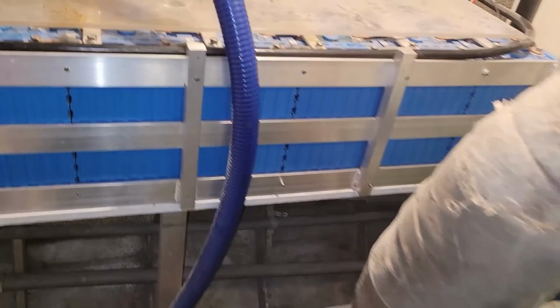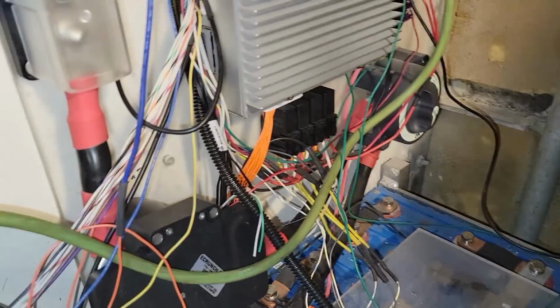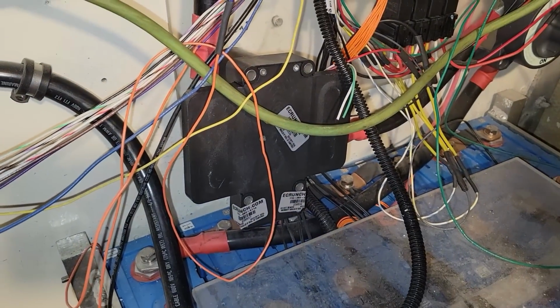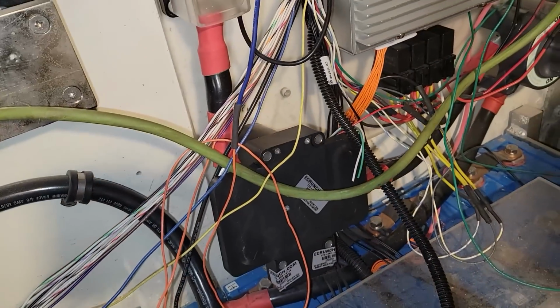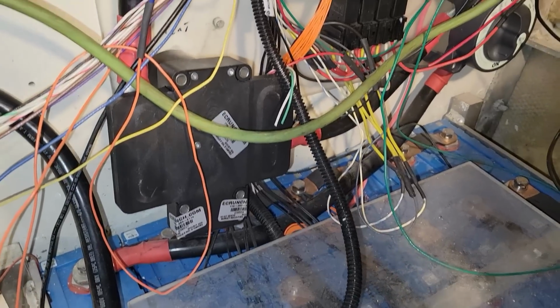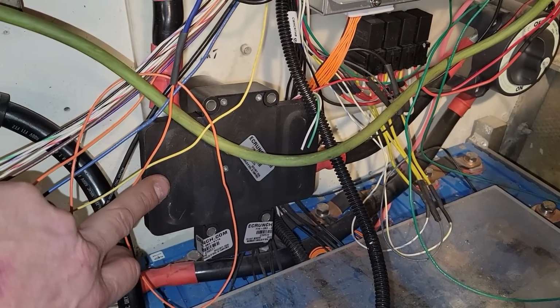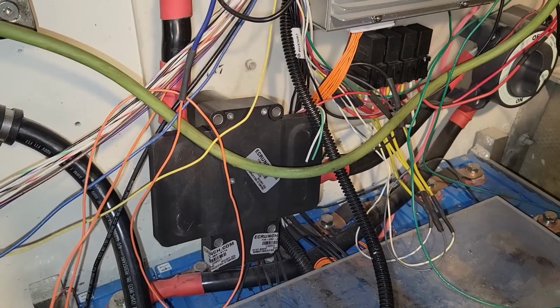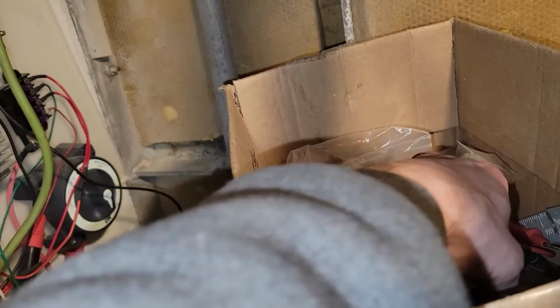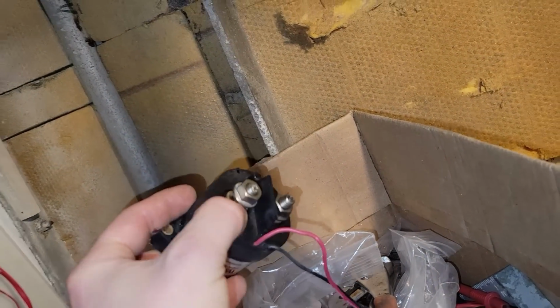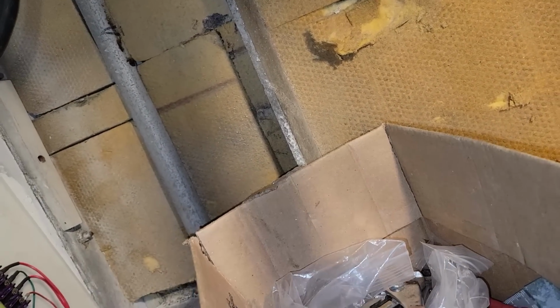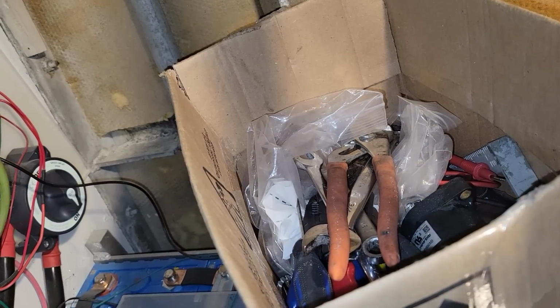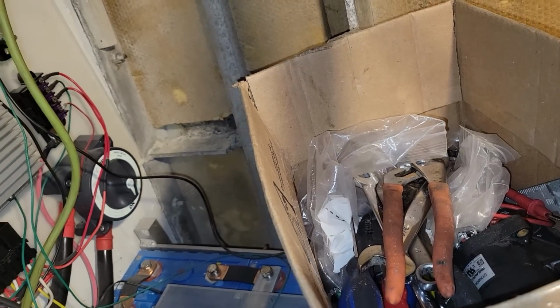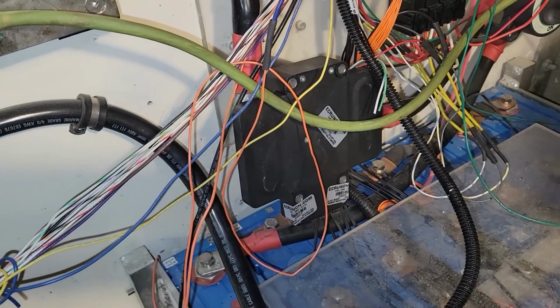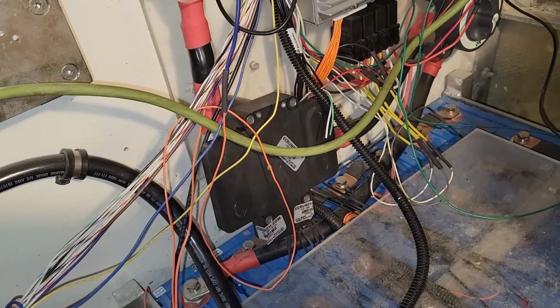Don't mind my back corner here, once again just doing some testing. I've also temporarily put in a larger contactor, a 1000 amp one. I had two 400 amp contactors, these little guys, bundled together with plates I made to tie them in parallel, but one or both of them were getting a bit warm. So I've got the new contactor temporarily wired in for testing, and we're going to try it to see what kind of amperage we get out of the generator now.